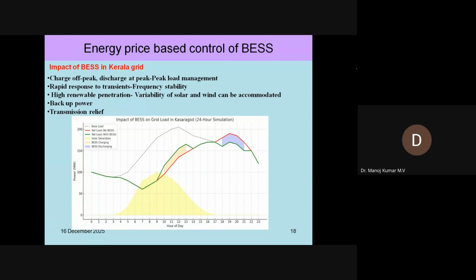Okay, so the impact of the battery energy - this is the example shown here. The particular region, the load is not that much high, it is around 150 or 175 megawatt only, and the battery storage comes around 20-25 megawatt, for 3 hours, so around 75 megawatt hour energy storage. That is only given here. This is the expected shape of the graph with the storage units coming into the picture.